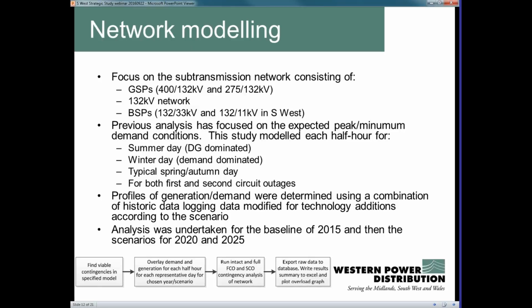One thing that was different about this modelling compared to what's been done previously is that we previously focused very much on peak half-hour, minimum half-hour type demand conditions. We recognise that load shapes and generation output profiles are changing as we get a different mix of generation. So we decided to model each half hour of three representative days to see where the worst conditions are, since it can be a combination of different demand and generation outputs causing issues.